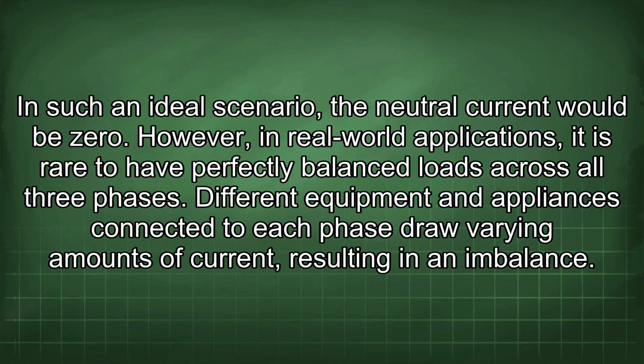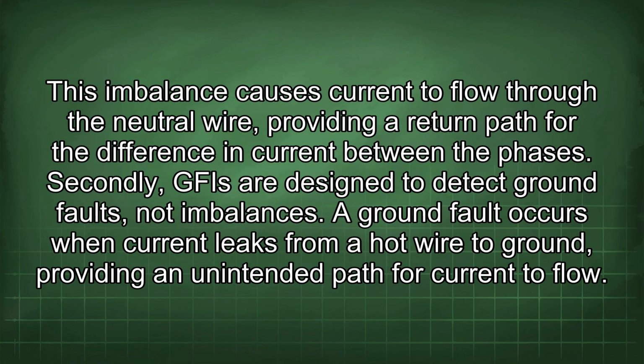However, in real-world applications, it is rare to have perfectly balanced loads across all three phases. Different equipment and appliances connected to each phase draw varying amounts of current, resulting in an imbalance. This imbalance causes current to flow through the neutral wire, providing a return path for the difference in current between the phases. Secondly, GFIs are designed to detect ground faults, not imbalances.